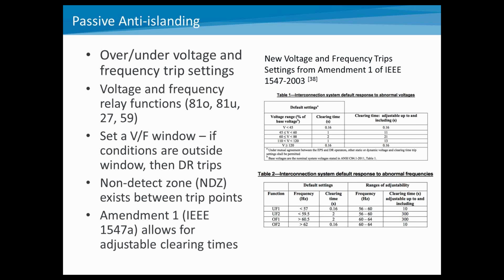And so if you are able to create a stable island condition, but your voltage and frequency don't go outside the normal operational areas, passive anti-islanding can be fooled. That being said, it's very difficult to maintain that matched real and reactive power setting with your distributed generation in there. The big thing here is that the new amendment to 1547 allows for adjustable clearing times.